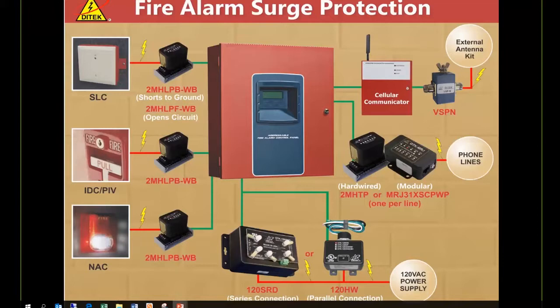Here at your SLC, you have 2 choices. You can go with our B series, 2MHLPB, which is a 5 amp max continuous operating current with base, 2-pair protection. And then also the 2MHLPF, which is perfect for SLC circuits. That is a 2-pair protector that we offer, best for that because that module does open instead of shorts. So when you have multiple buildings, like a garden-style apartment, where you have multiple buildings in the circuit, your best product there is to use the 2MHLPF. So if that device does ever compromise, even though they are self-restoring, self-resetting, it will open. That way you can find out exactly where that module has compromised, replace it, and you're up and running.